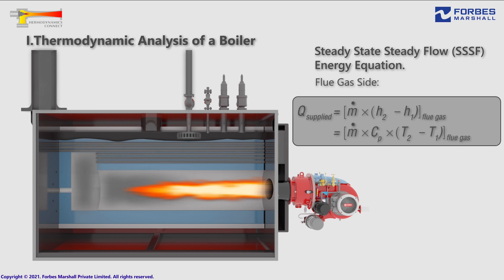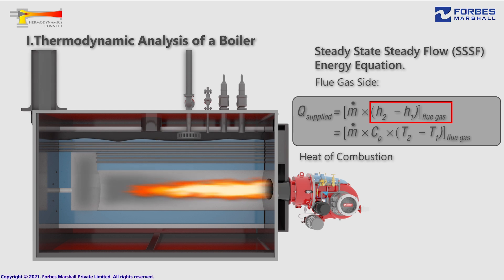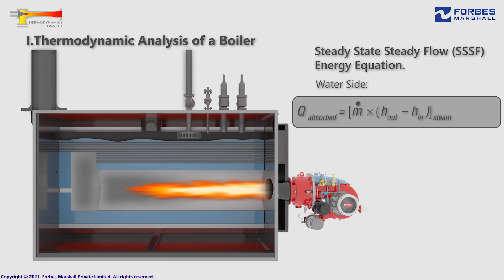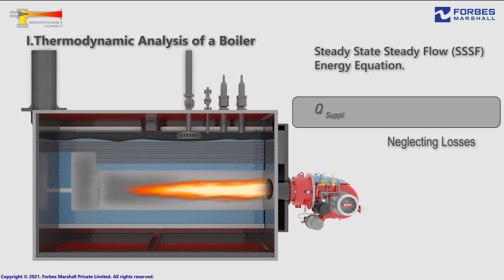Thus, in a boiler, for the flue gas side, the heat supplied is the heat supplied by the combustion of the fuel, which is essentially the change in enthalpy of the flue gas as it loses its heat from the highest temperature point at the burner to the lowest temperature point at the exit of the third pass. The heat absorbed by water is the difference in enthalpy of inlet water and produced steam. Finally, neglecting losses, we conclude that the heat supplied by the flue gases inside the boiler is the same as the heat gained by the boiling water under the steady state and steady flow conditions.